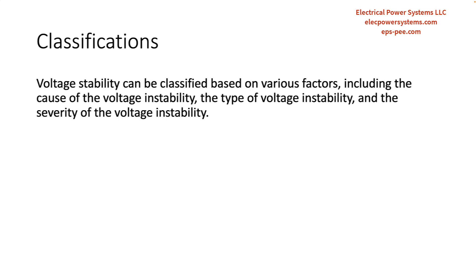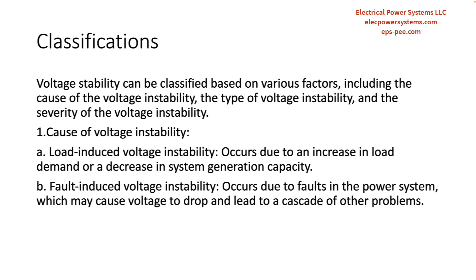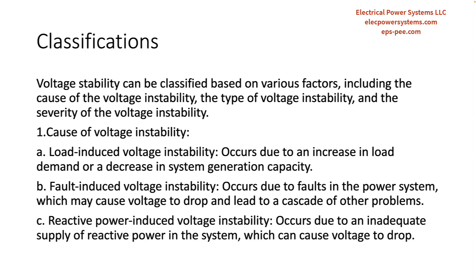Voltage stability can be classified based on various factors, including the cause of the voltage instability, the type, and the severity. Regarding the cause: load-induced voltage instability occurs due to an increase in load demand or a decrease in system generation capacity; fault-induced voltage instability occurs due to faults in the power system, which may cause voltage to drop and lead to a cascade of other problems; and reactive power-induced voltage instability occurs due to an inadequate supply of reactive power, which can cause voltage to drop.